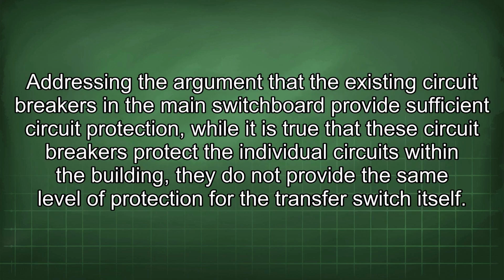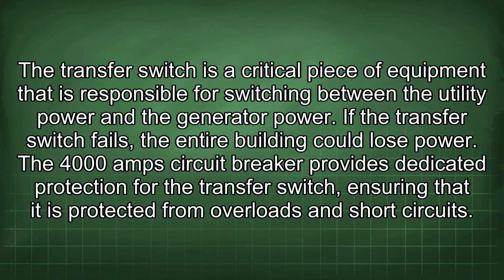Addressing the argument that the existing circuit breakers in the main switchboard provide sufficient circuit protection, while it is true that these circuit breakers protect the individual circuits within the building, they do not provide the same level of protection for the transfer switch itself. The transfer switch is a critical piece of equipment that is responsible for switching between the utility power and the generator power. If the transfer switch fails, the entire building could lose power.